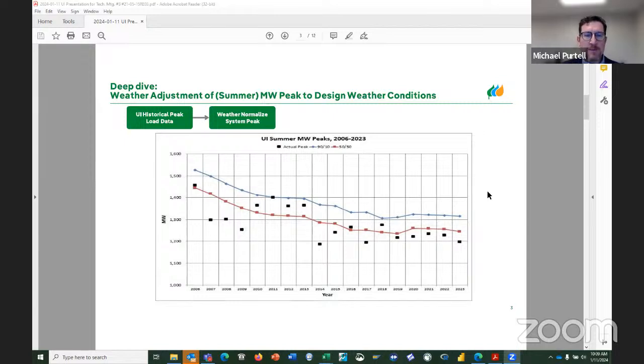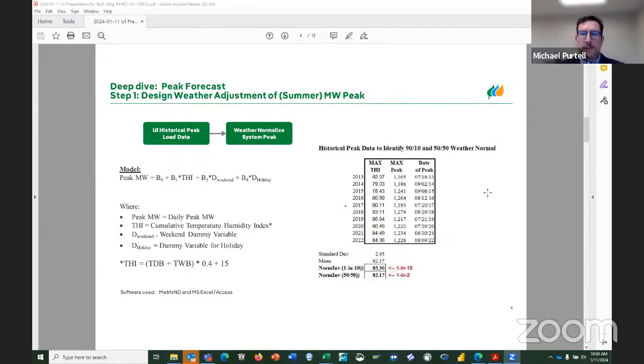So how do we do these types of adjustments? Our peak forecast is really a two-step process. Our first step is to analyze the most recent summer, the daily peaks, and then estimate the weather response and adjust that to the design conditions. And since we're talking distribution planning, our design condition is a 90-10. I'm sorry, 1 in 10, probability of occurrence of 10%. So we calculate that on the table on the right here.